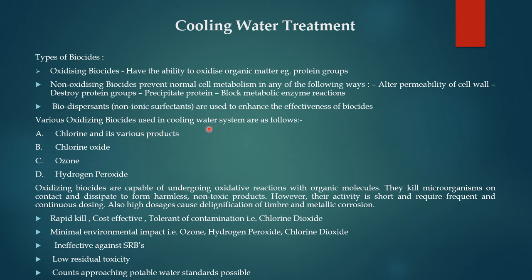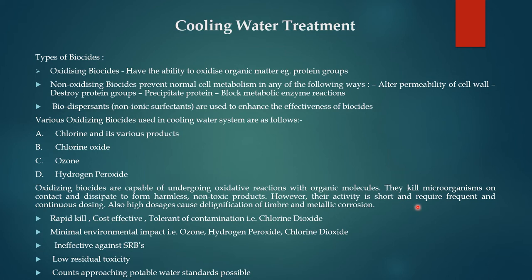Various oxidizing biocides used in cooling water systems include chlorine and its various products such as chlorine dioxide, ozone, and hydrogen peroxide. Oxidizing biocides are capable of undergoing oxidative reactions with organic molecules; they kill microorganisms and dissipate to form harmless non-toxic products. However, the reactivity is short and requires frequent and continuous dosing. High dosages can cause de-lignification of timber and metallic corrosion. Chlorine is dosed continuously to maintain free residual chlorine, with periodic shock dosing to completely kill microorganisms.